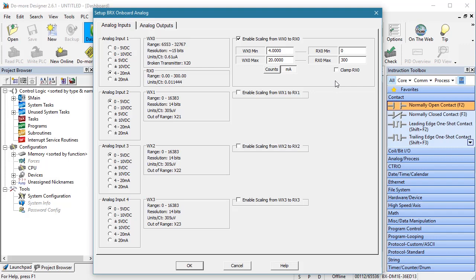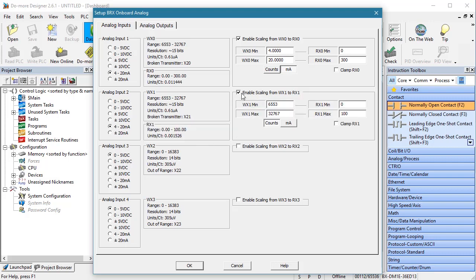Notice that Do-more Designer has already taken the 4 milliamp offset into account. That is, 4 milliamps corresponds to this digital value. I love that I don't have to remember how to do that. And the final scaled temperature data is in RX0. Now we still have the room temperature sensor connected and the BRX PLC will complain if we don't configure it, so I'll go ahead and set that up so we can monitor the room temperature if we want to.